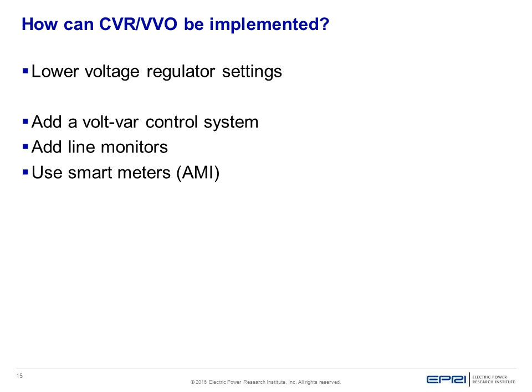The next level of sophistication is that you can also apply improvements to the distribution system that will allow you to more uniformly drop the voltage to customers. It generally translates that the lower the voltage, the greater the energy savings. So if we can make sure that the voltage is more evenly applied to customers, there's less voltage drop, and we can get more voltage drop to more customers.